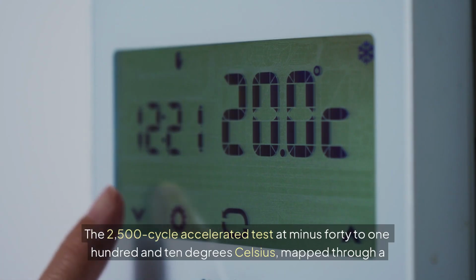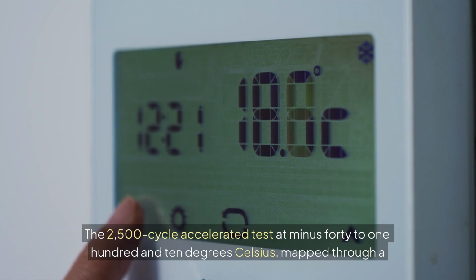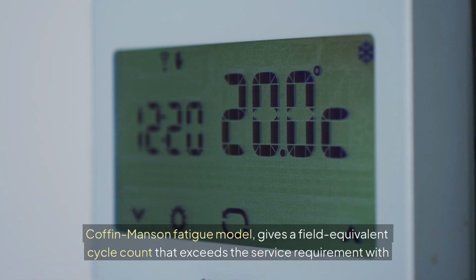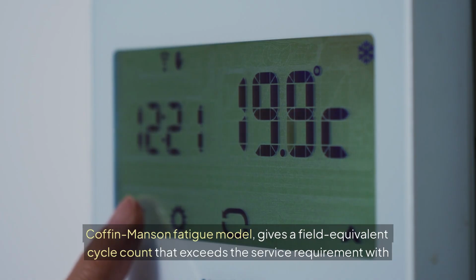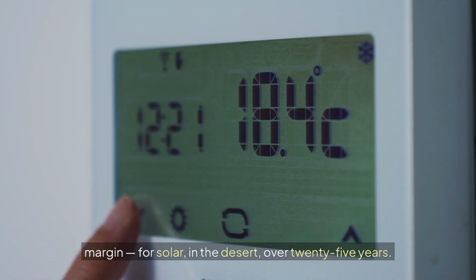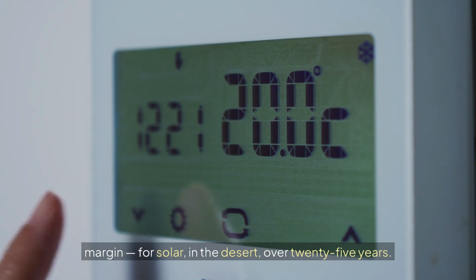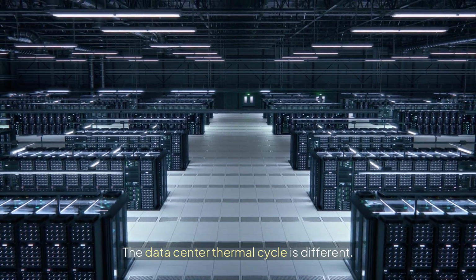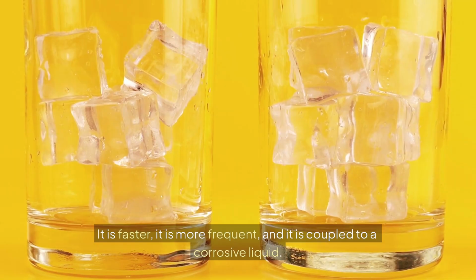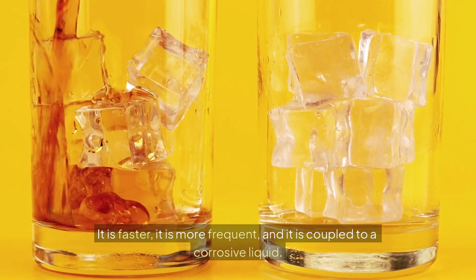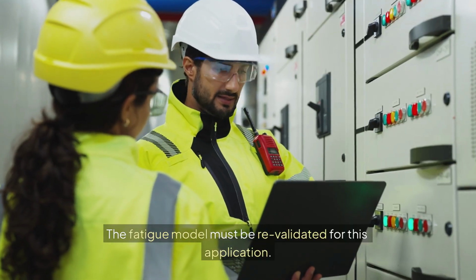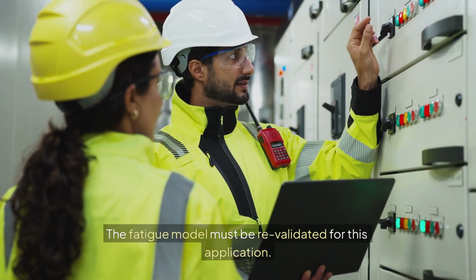The 2,500 cycle accelerated test at -40 to 110 degrees Celsius, mapped through a Coffin-Manson fatigue model, gives a field equivalent cycle count that exceeds the service requirement with margin for solar in the desert over 25 years. The data center thermal cycle is different. It is faster, it is more frequent, and it is coupled to a corrosive liquid. The fatigue model must be revalidated for this application.